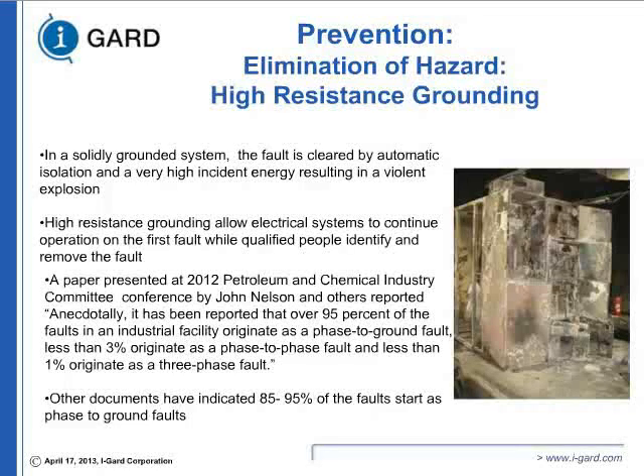A paper presented at the 2012 Petroleum and Chemical Industry Conference by IEEE fellow John Nelson quoted: anecdotally it has been reported that 95% of faults in an industrial facility originate as phase-to-ground faults. Less than 3% originate as phase-to-phase faults, and less than 1% originate as three-phase faults. So if you are using high resistance grounding and you maintain it properly, your probability of having an explosion is cut down by 95%. Okay?